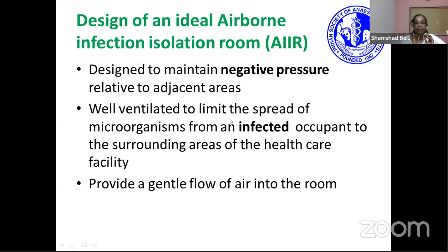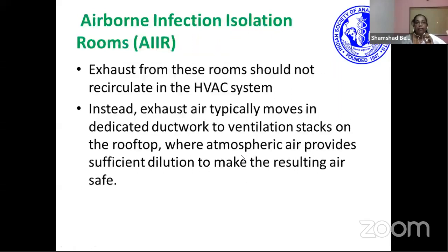It should be well ventilated to limit the spread of microorganisms from an infected occupant to the surrounding areas of the healthcare facility, providing a general flow of air into the room. The exhaust from these rooms should not recirculate in the HVAC system.